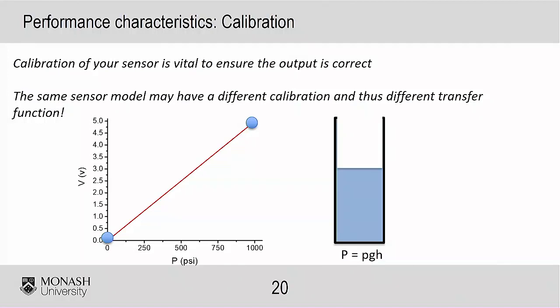One of the things that we do is we have probably about 12 pressure sensors, all in a large mechanical system that represents your heart and your circulatory system. It's called a mock circulation loop. Think of it as an artificial heart and circulatory system. It sits on the bench. It beats away just like your normal heart does. And so we need to measure pressures all over this system.